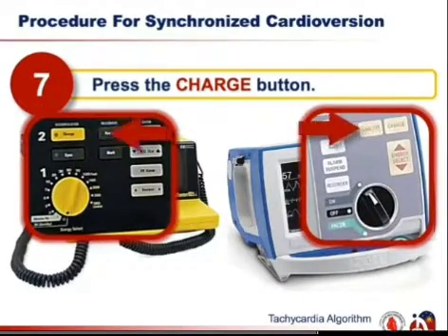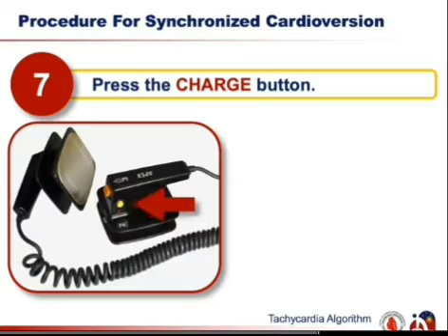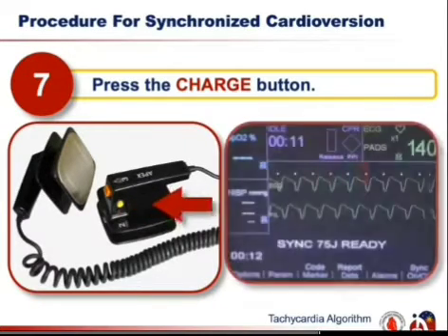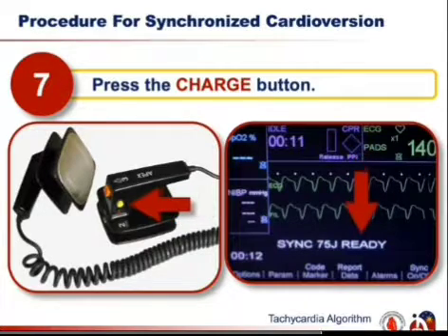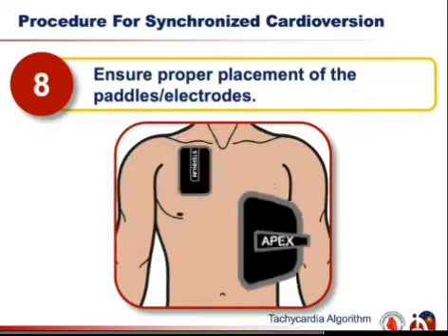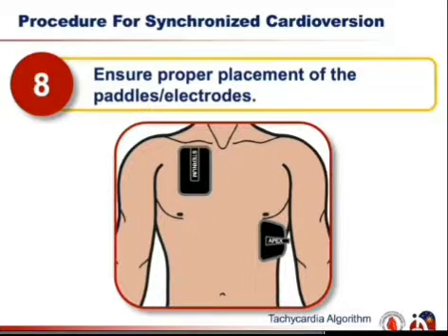Step 7. Press the Charge button. You can also press the yellow button on the paddles to charge. Once charged, the word Ready will be displayed on the screen. Step 8. Ensure proper placement of the paddles and electrodes, following these anterior lateral positions.